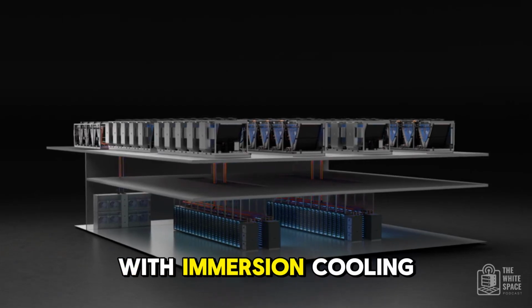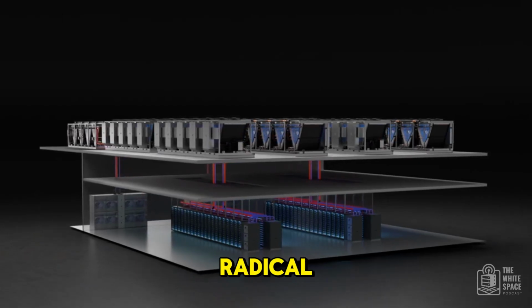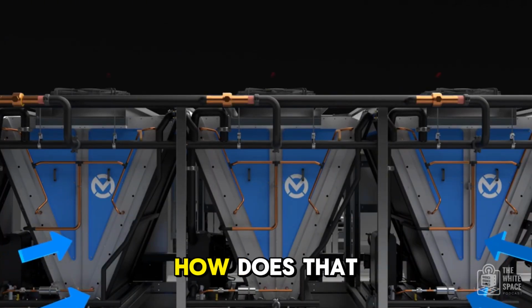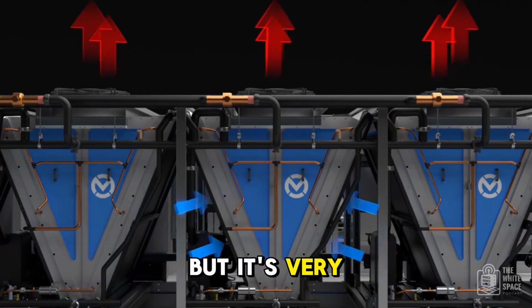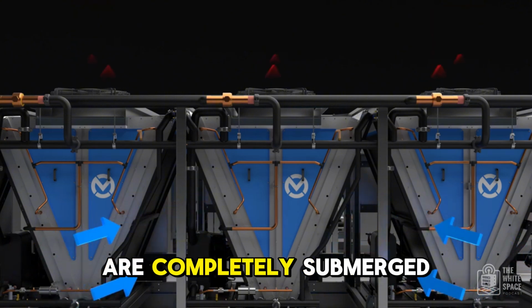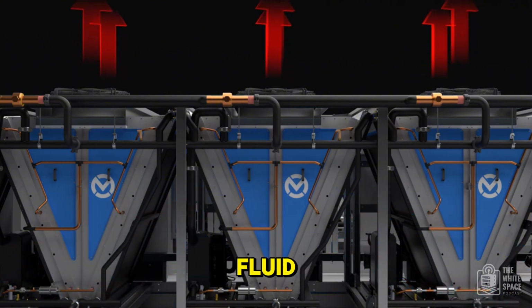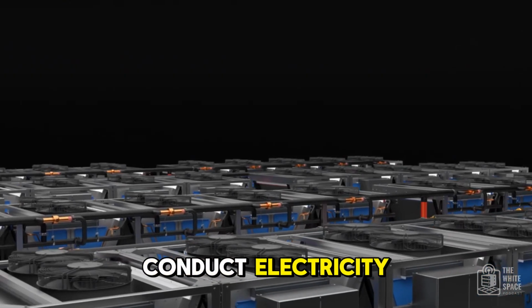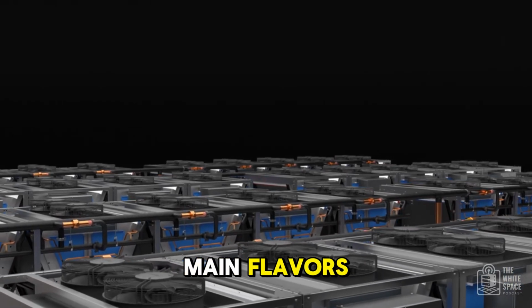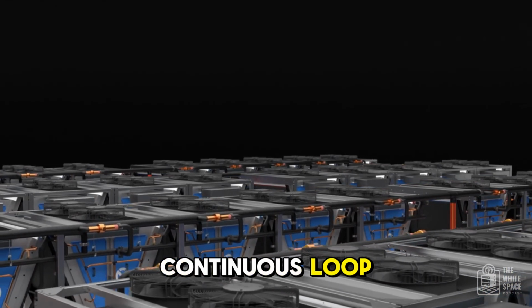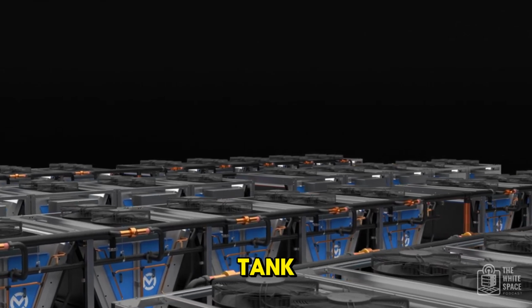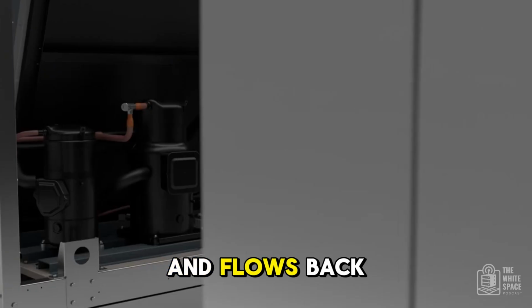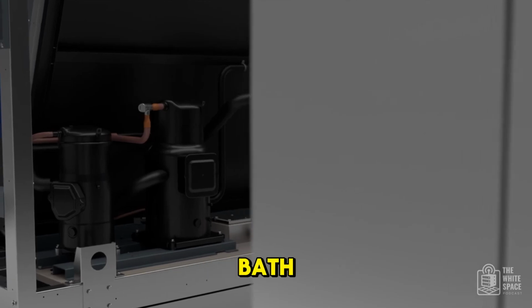Okay, let's start with immersion cooling. That sounds pretty radical, like dunking your servers in a bath. How does that work? It does sound wild, but it's very effective. The servers are completely submerged in a dielectric fluid. Crucially, it doesn't conduct electricity. There are two main flavors. Single-phase immersion is like a continuous loop. The fluid flows out of the tank, it's cooled by a heat exchanger, and flows back in. Kind of like a constant cool bath, yeah.